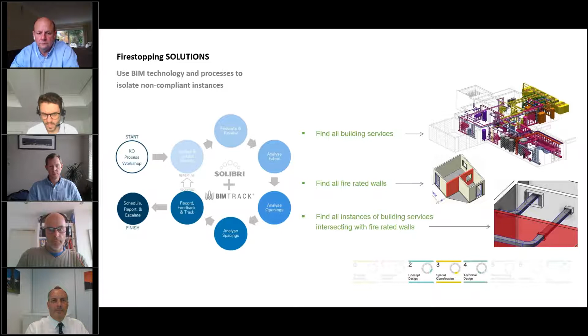That's what we do with the rule set in the first instance. Once we've identified how many services are penetrating fire-rated fabric, we check the distances between the edges of things like cable trays and the edge of the opening, to make sure there's enough firestop product around it to be compliant — or whether there's enough space between a cable tray and another pipe penetrating the same firestop. This is about checking for and demonstrating compliance.